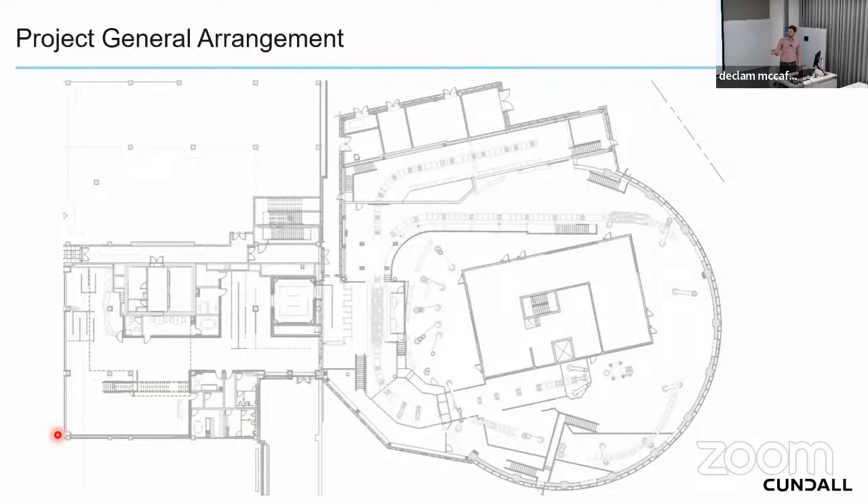On the ground floor plan: on the left is the mall fit-out with ticketing, a pre-show experience, offices, and toilets; then you walk into the load/unload station where the roller coaster journey starts. In the middle is the central core and a private substation — the LSM magnetic motors require an unusual electrical demand: all power instantaneously for five seconds, then nothing for three minutes, then full power again. So we needed our own private network. Above, there's a maintenance area where trains undergo servicing outside public view, and further up is MEP with generators, RMU, and HV switchrooms.